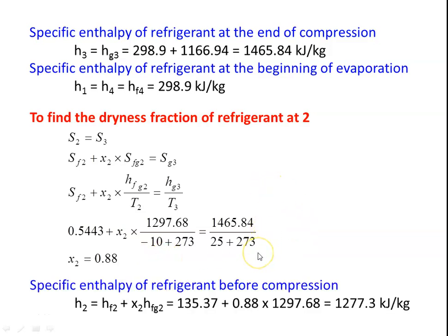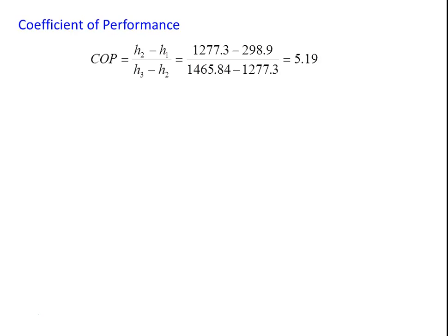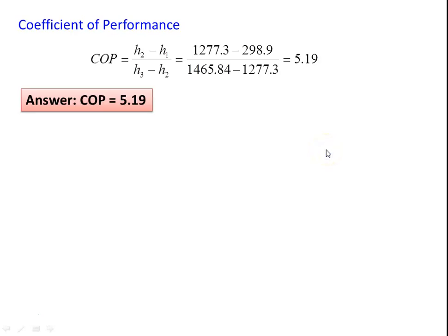The specific enthalpy of the refrigerant before compression: H2 = HF2 + X2 × HfG2 = 135.37 + 0.88 × 1297.68 = 1277.3 kJ/kg. Calculating the COP = (H2 - H1) / (H3 - H2), substituting all values gives COP = 5.19.